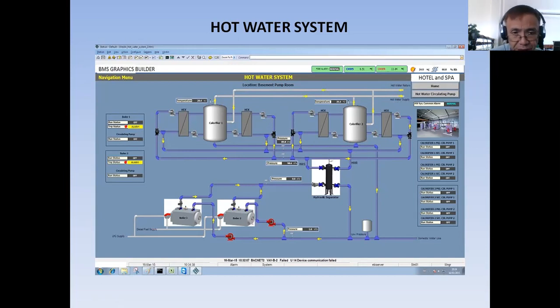As you can see here, I have two calorifiers and I have four heat exchangers. You know already what's the purpose of heat exchanger. I have two boilers here, one duty and one standby, then I have two water supply and I have a separator, hydraulic separator that separates the air and some of the dirt that might enter the boiler water supply.